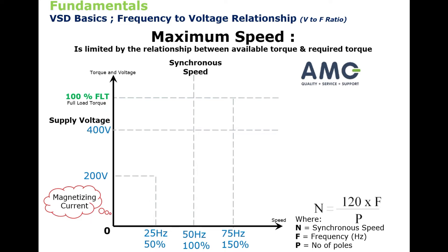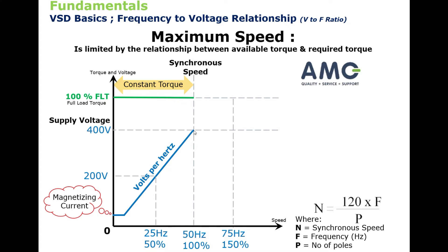When voltage is applied to a motor, enough current flows to magnetize the iron. At half speed, the frequency of the inverter will be 25 Hertz and the voltage across the windings will be 200 volts. At full speed or synchronous speed, the voltage across the windings will be 400 volts.